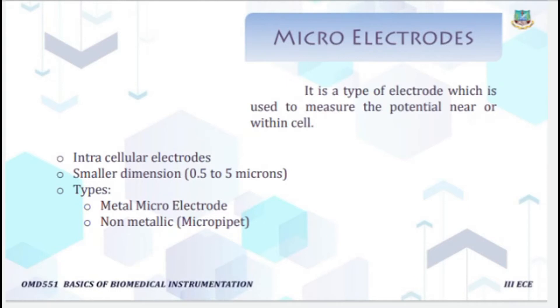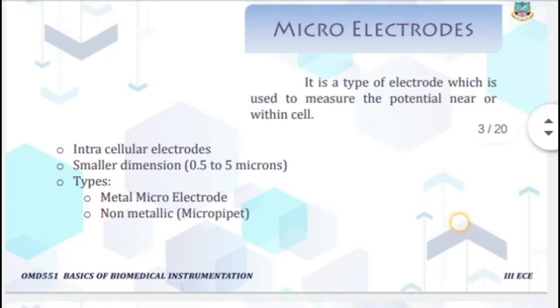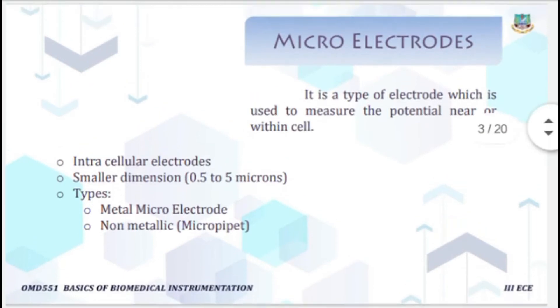What is a micro electrode? Micro electrodes are used to measure the bioelectric potential near or within a single cell. They are also called intracellular electrodes. Micro electrodes are divided into metallic and non-metallic types. They have a small diameter so that during insertion into the cell, they will not cause any damage. During potential measurement, the micro electrode is placed within the cell and the reference electrode is placed outside the cell.